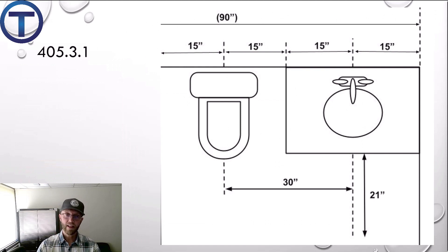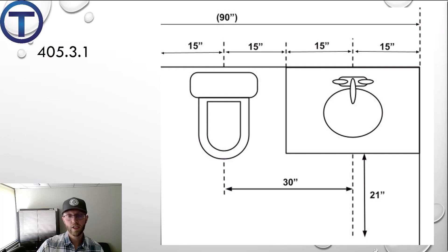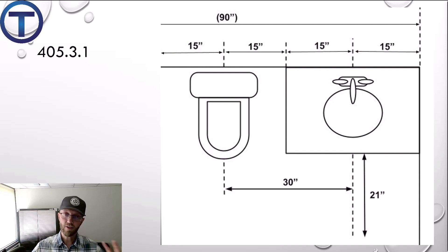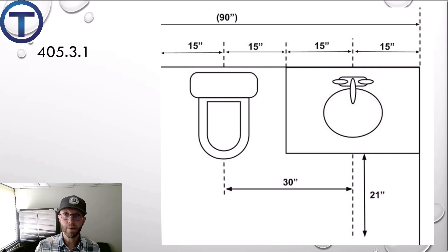You should definitely memorize: 15 inches away from a finished wall to the center of the fixture, 30 inches center to center between fixtures, and 21 inches out in front. This gives you the ability to figure out restrooms. Even on a plan that may not have everything spelled out, you know your minimums and can lay out a restroom.